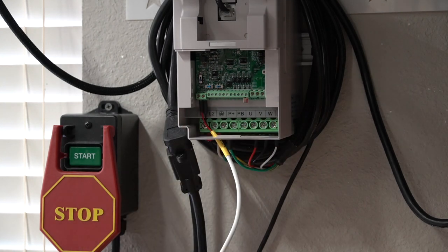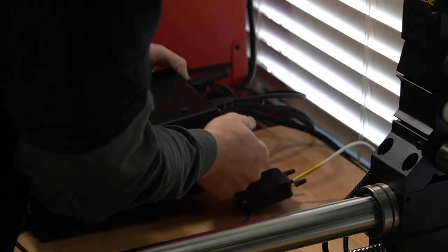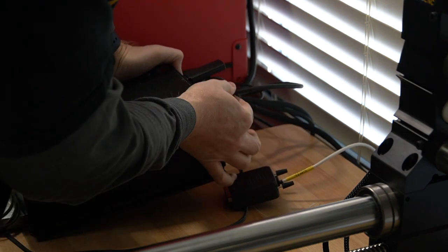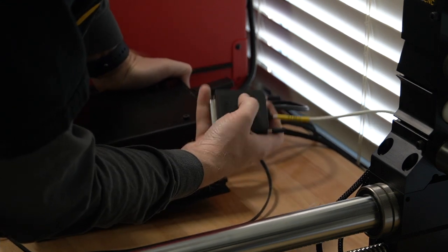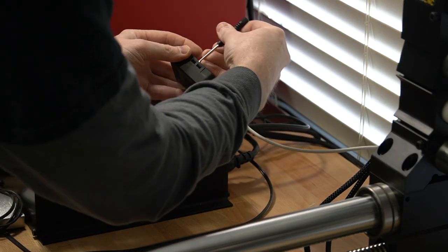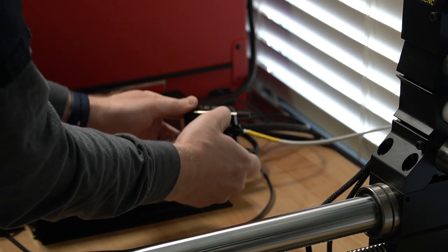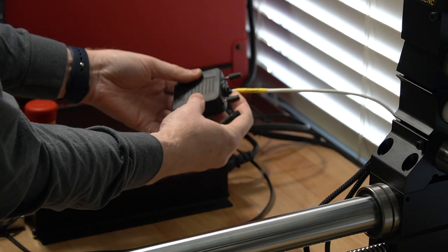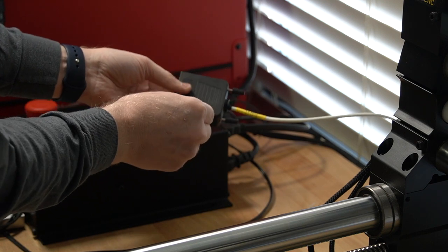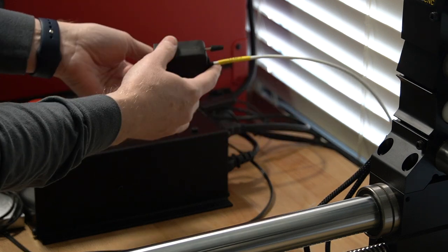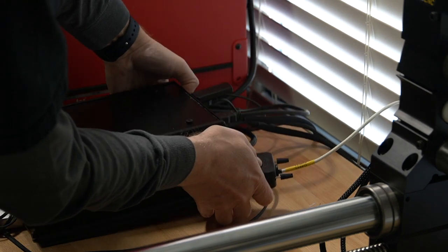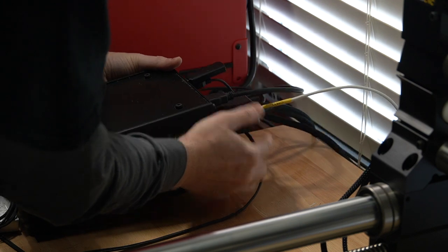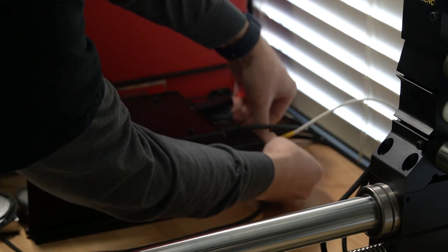So let's switch over to the back of the controller. Okay I have a really weird angle here and everything's kind of got tight cables so it's really hard for me to pull this out. But in between the HDMI cable and the power cable there's a DB25 connector. The three wires we're concerned with is number 13, 14, and the ground. The ground shields our, is the drain for our shielded cable here. So we've got the connector right on the back in between the power and the HDMI. All we do is plug it in, tighten down the terminal screws and your installation is done.